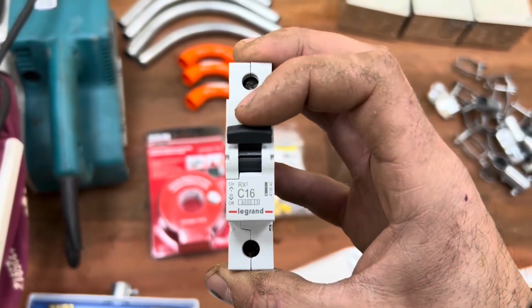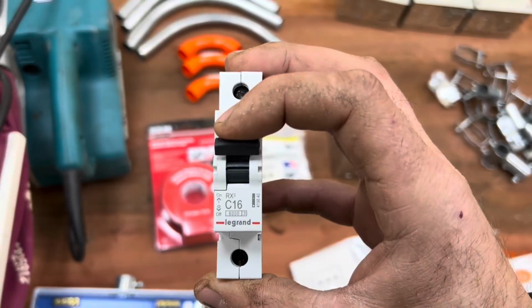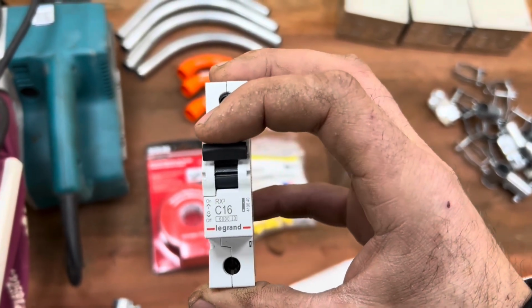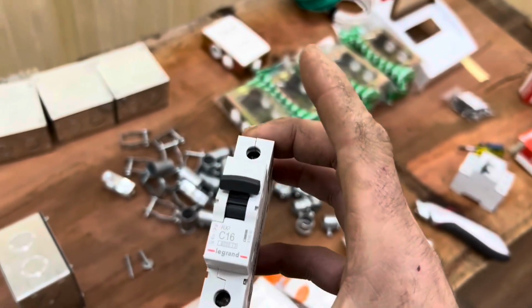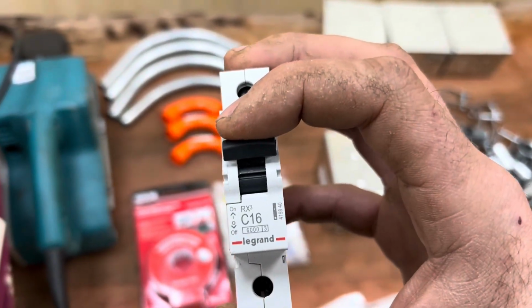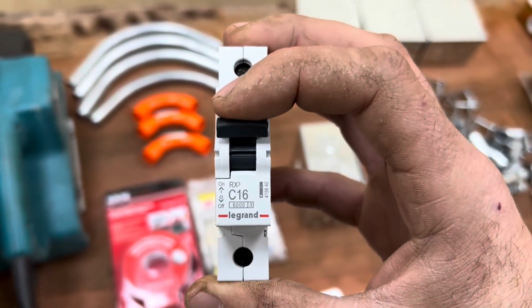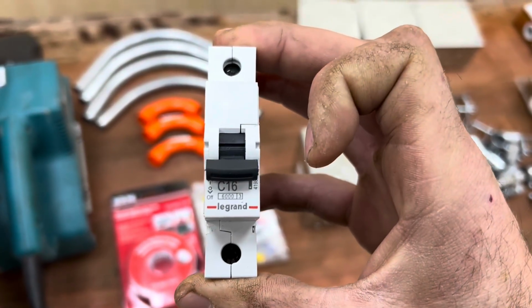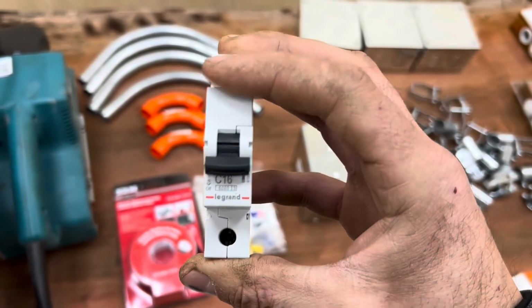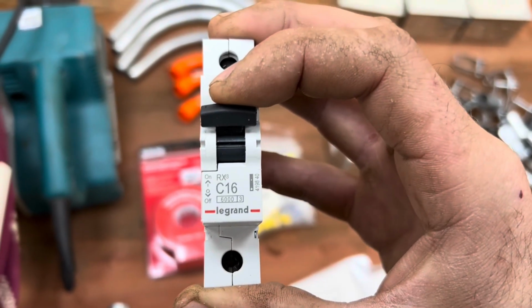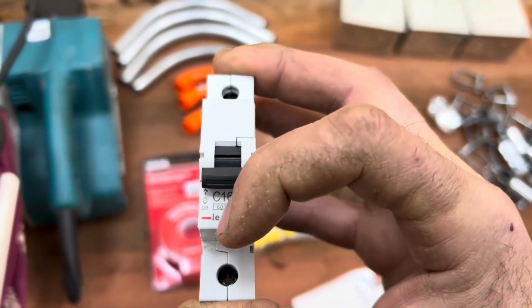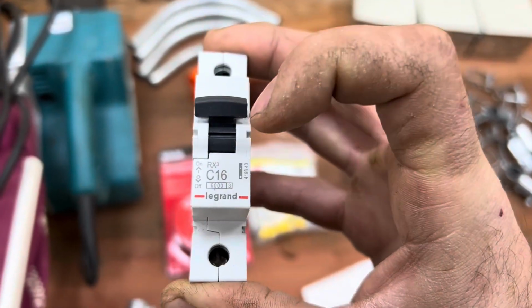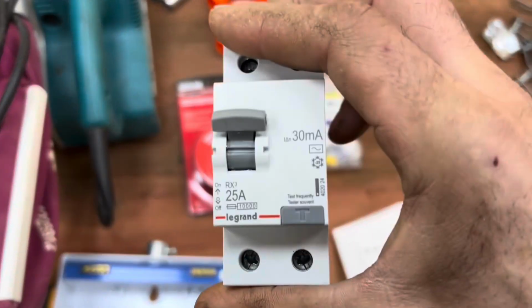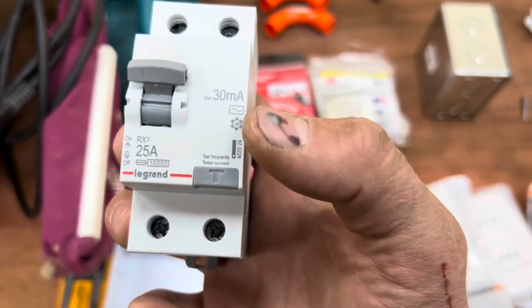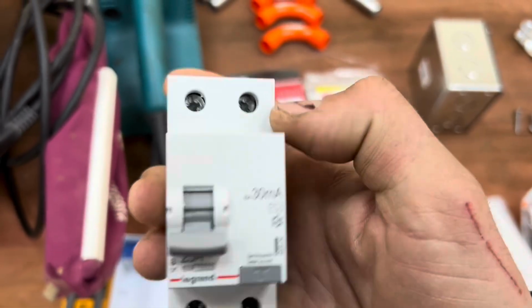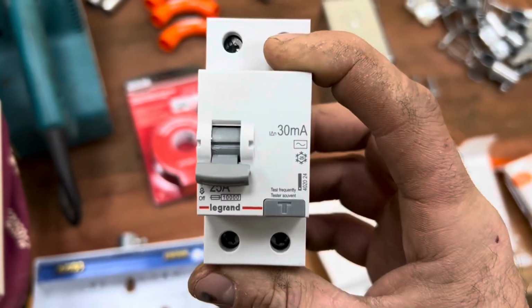The idea is that if we go over the 16 amp limit and we're using tools or consuming a lot of electricity, to prevent those 2.5 millimeter cables from heating up or eventually getting damaged, melting, or causing a fire, this switch will trip first, so our protection is our guarantee. The idea is that the switch trips before the cables heat up. For 2.5 cables, 16 amps is perfect. And the differential is to protect us. If we get an electric shock, this will trip immediately. Very important, since it can save our lives.